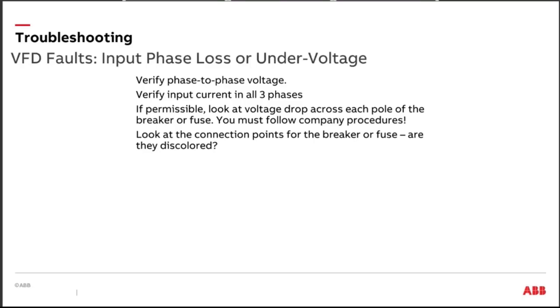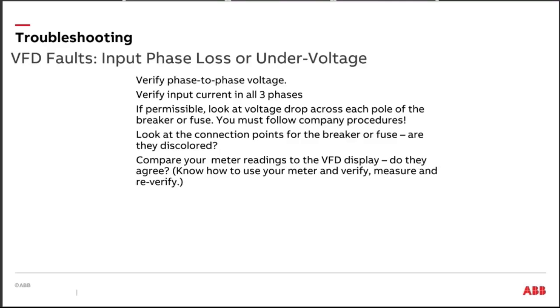Okay, look for something discolored. Is it chemical? Okay, is it biological? Are you out on the coast somewhere and I have salt air and that's causing my problems with my connection? Those are the things that I think about on input phase loss or an undervoltage. It's not necessarily just the power that's coming into the drive. It might be what's associated with getting the power into the drive.